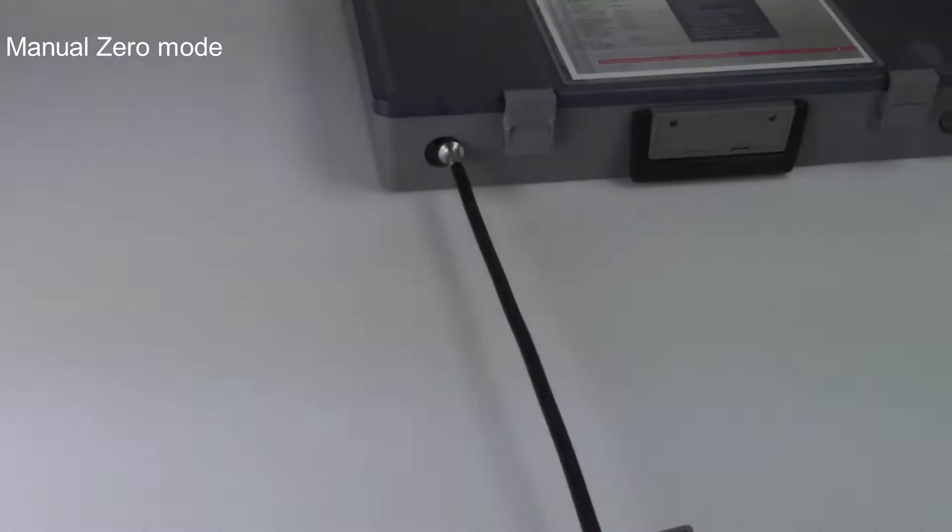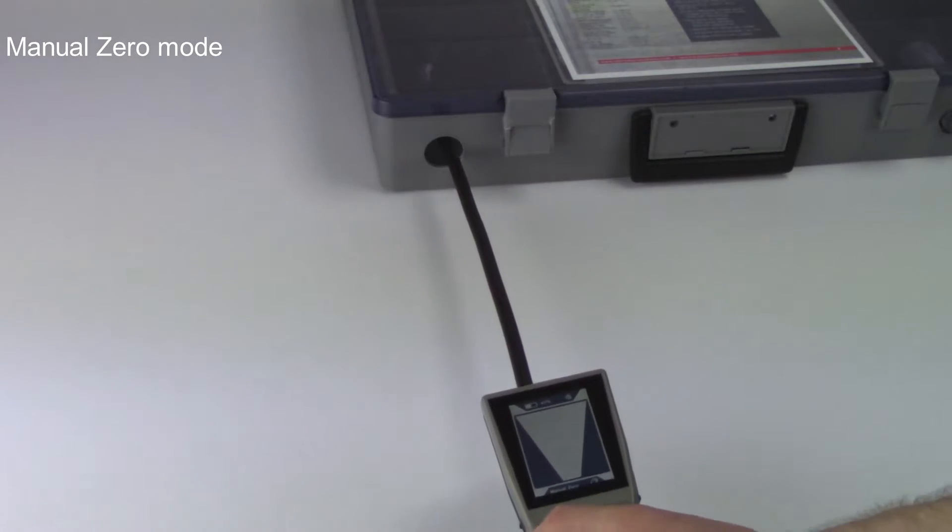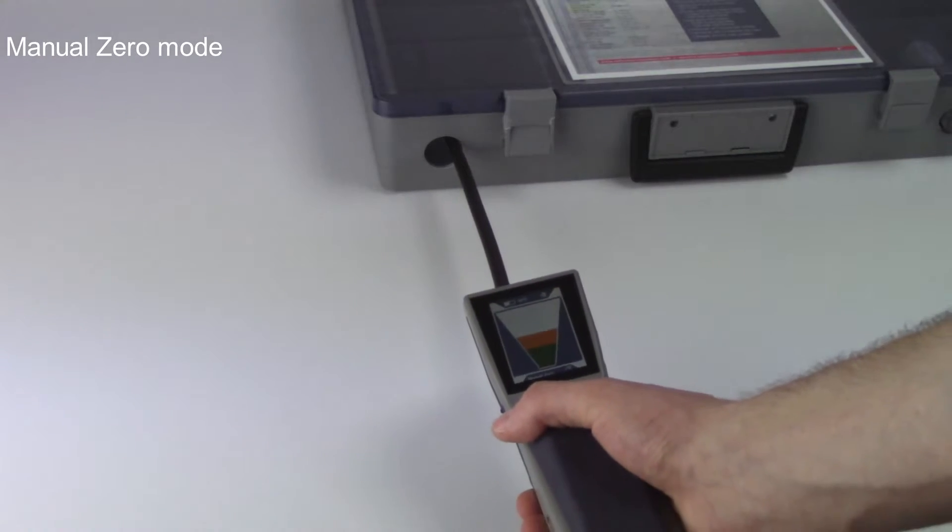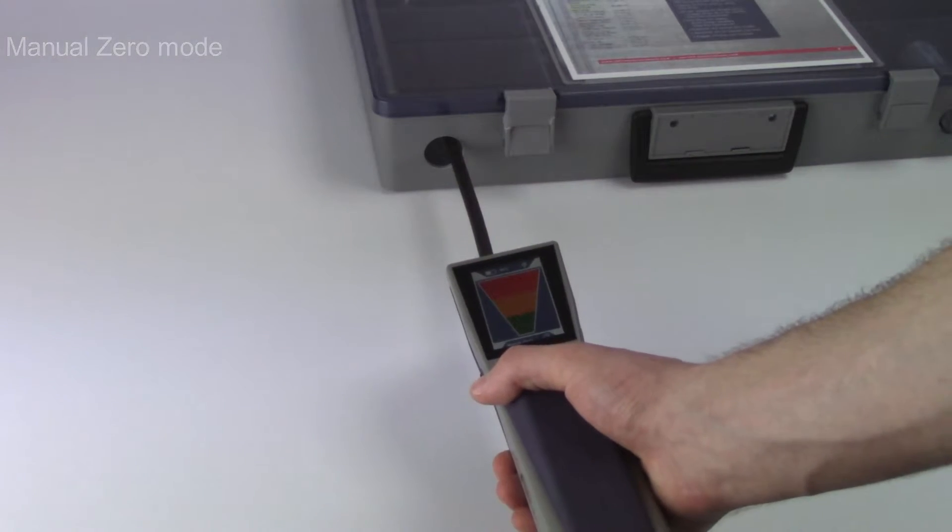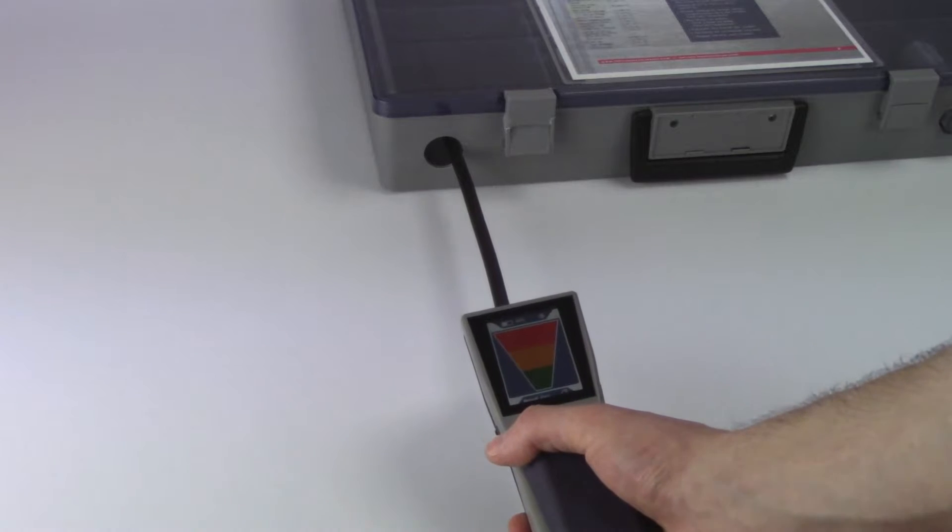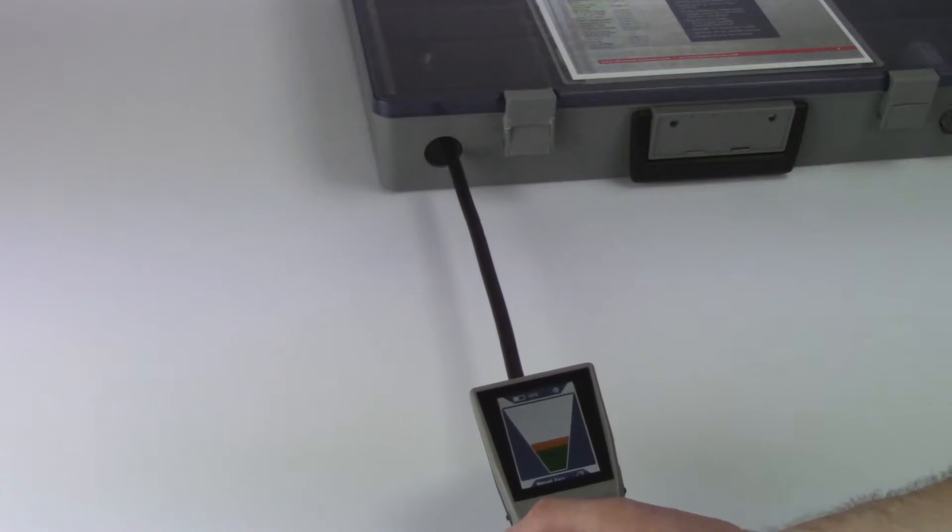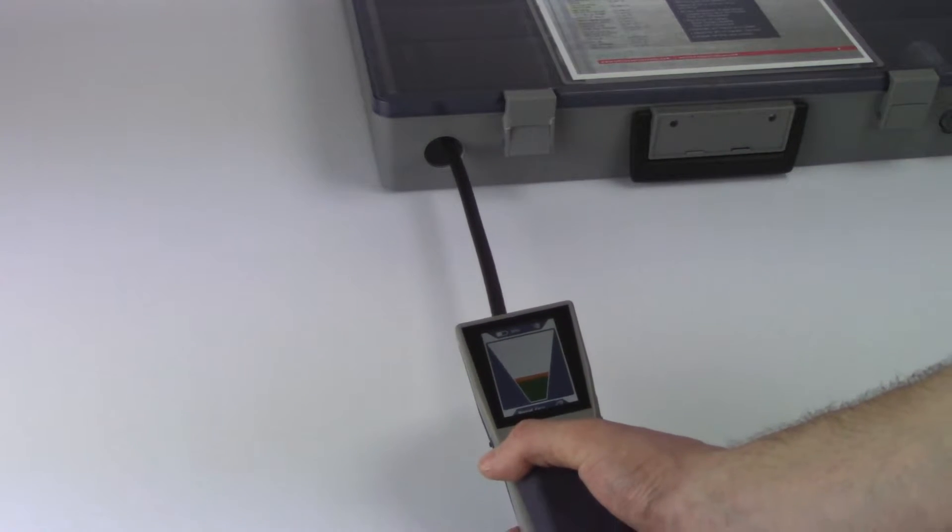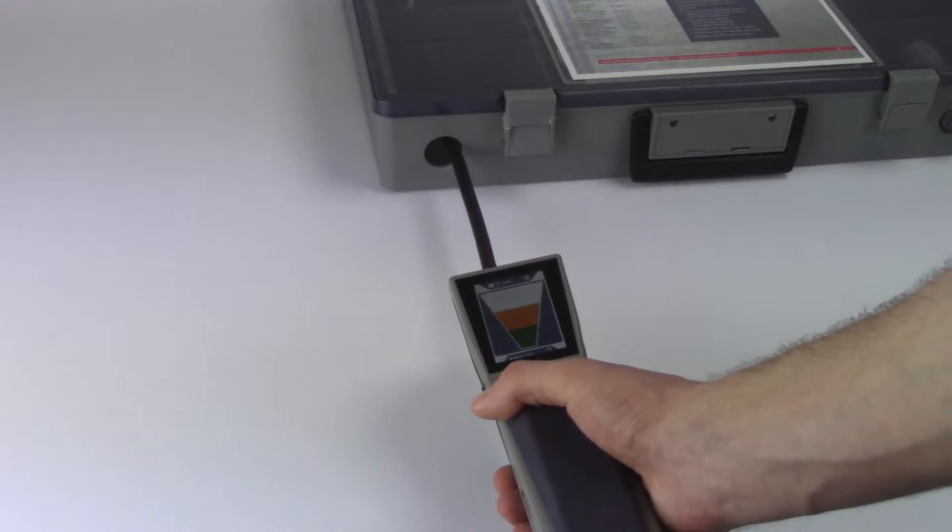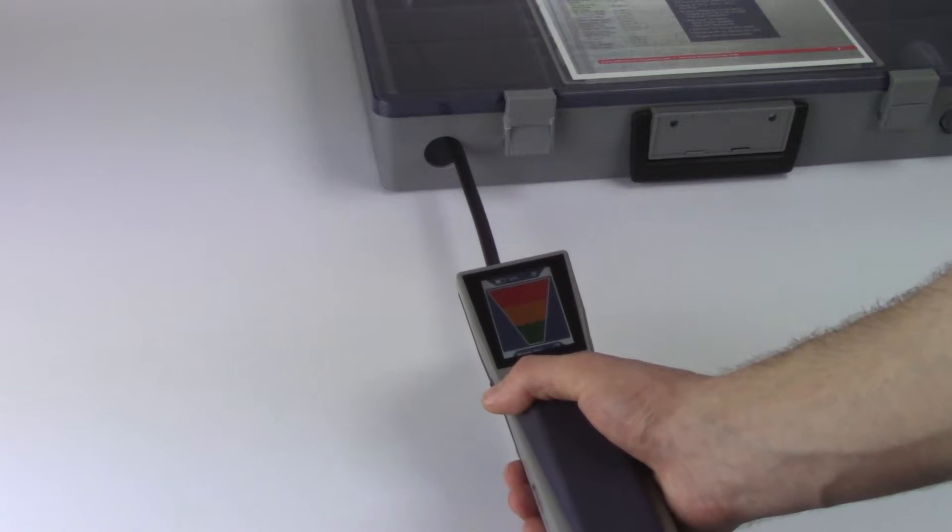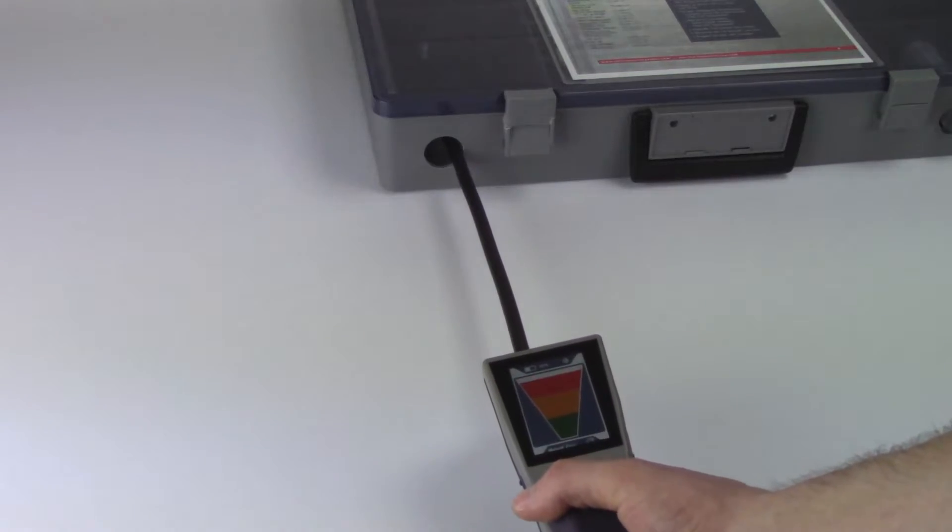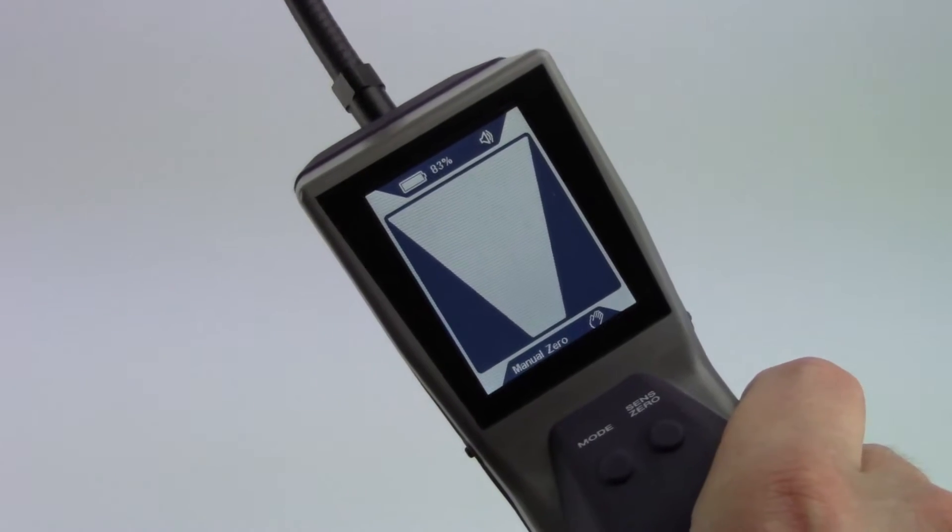While in Manual zero mode, the beep rate is faster and increases or decreases with the change in background concentration. This means that if the beeping quickens, you're closer to the leak. If the beeping slows, you're further away.